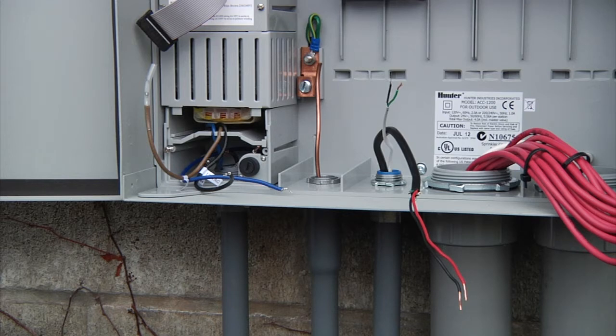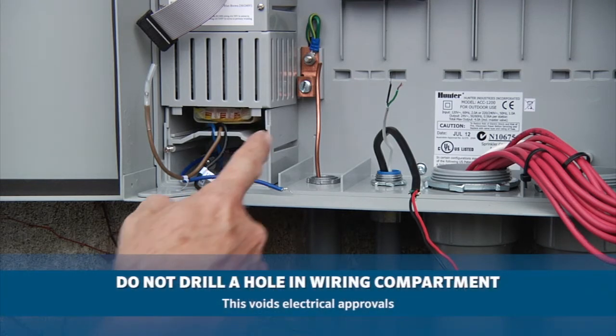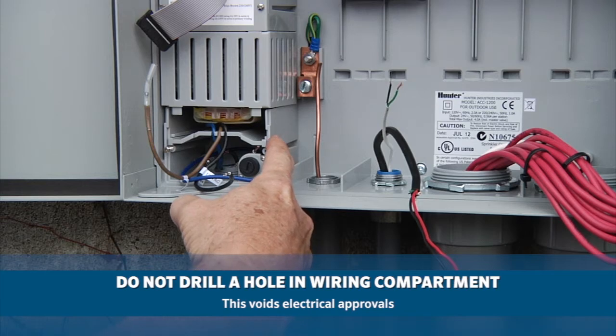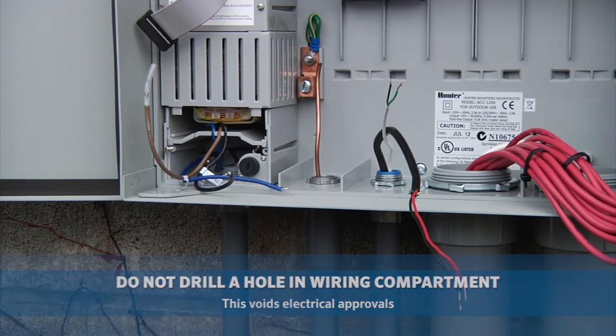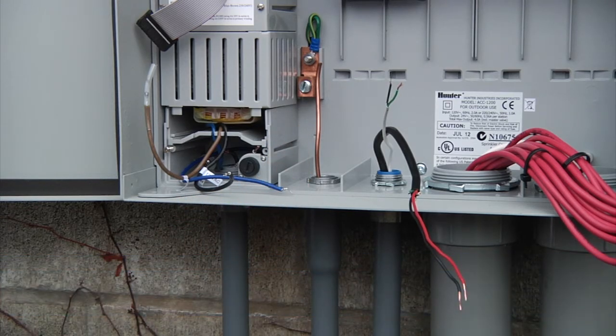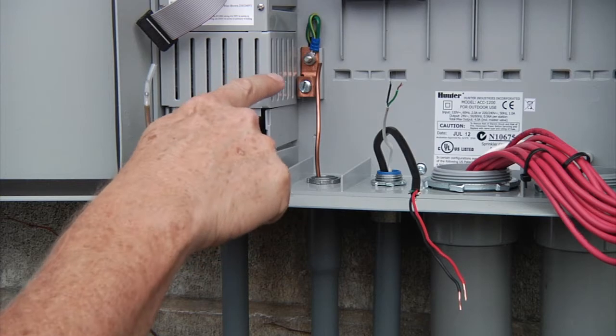In some countries, such as Australia, it is specifically prohibited to connect the incoming electrical safety ground to the earth ground lug. If you decide to connect the safety ground from the electrical service to the lug, do not drill a hole in the wiring compartment. This voids the electrical approvals. Instead, run the electrical ground through a T-junction below the controller and route it up through one of the smaller conduit openings to the lug.